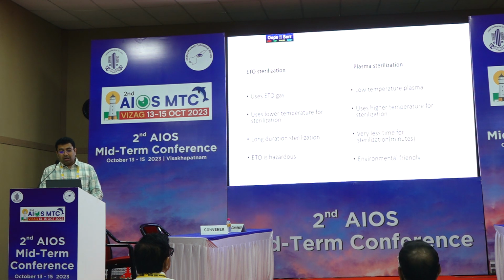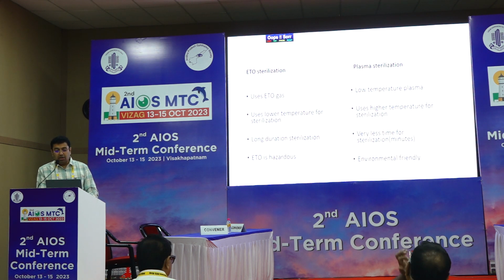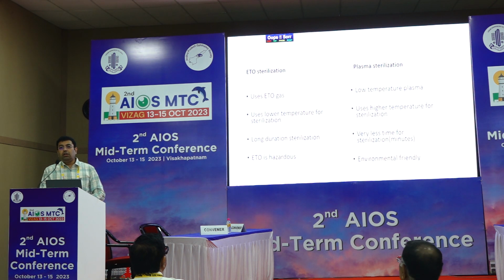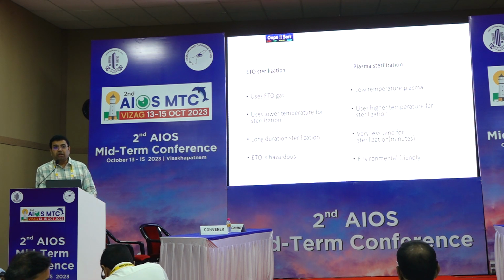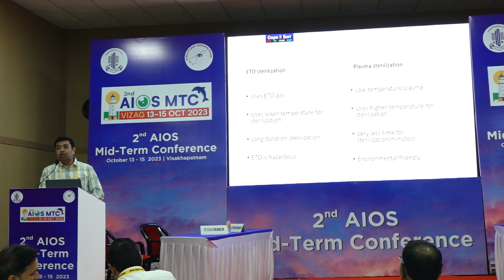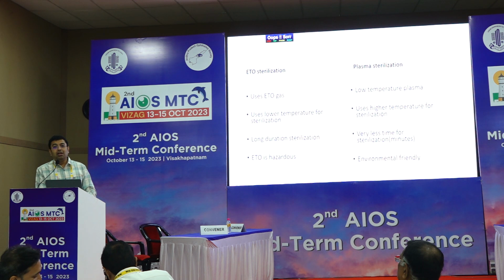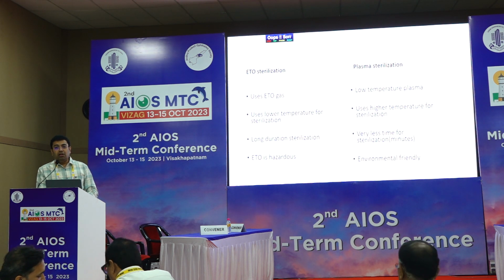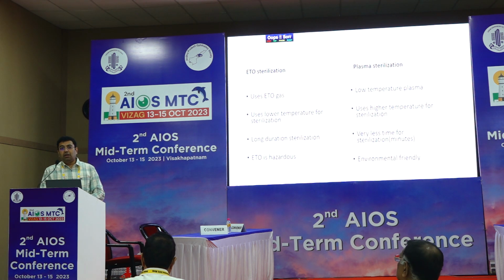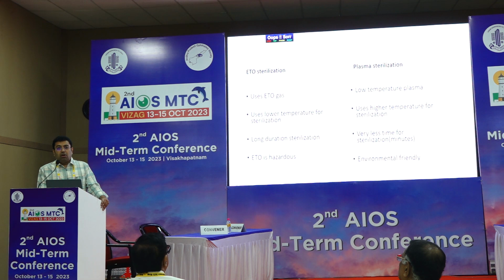The one advantage with plasma sterilization is that it is a fast sterilizer. Usually it takes about 75 minutes to complete a sterilization, whereas ETO has the advantage that it works much better than a plasma sterilizer. But the important disadvantage with the ETO sterilizer is that it is a long duration sterilizer. Usually an ETO sterilization process takes 6 to 10 hours, so you have to keep it overnight for sterilization. Another disadvantage is that ETO is a hazardous, toxic and cancer-causing gas, so you should always have a proper aeration system in your hospital to see that ETO is properly disposed.